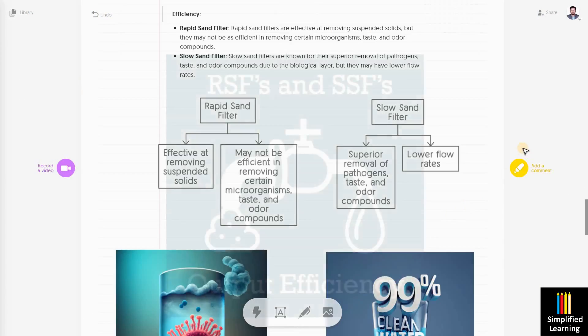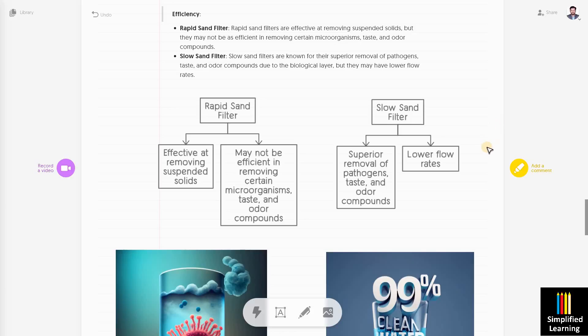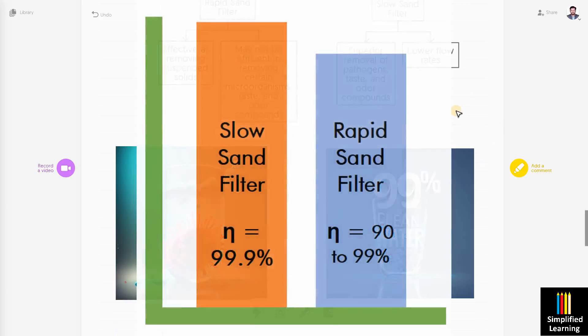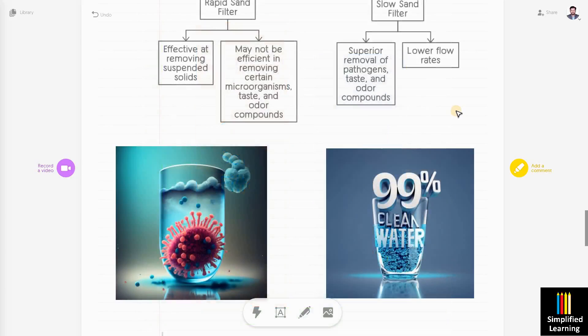Both rapid sand filter and slow sand filter are very efficient. In rapid sand filter, about 90 to 99% of bacteria are removed. In slow sand filter, about 99.9% clean water is achieved. Slow sand filter also provides removal of pathogens, taste, and odor, whereas rapid sand filter is not as efficient at removing certain bacteria, microorganisms, taste, and odor elements.